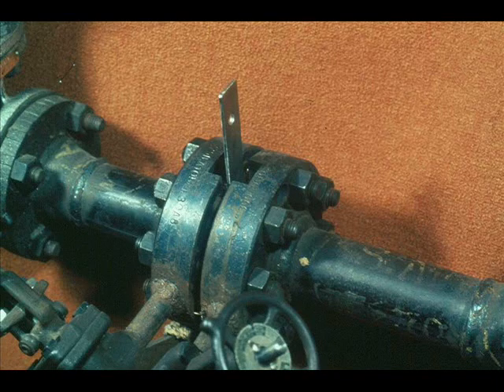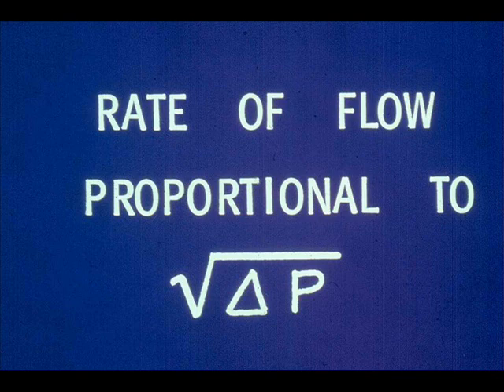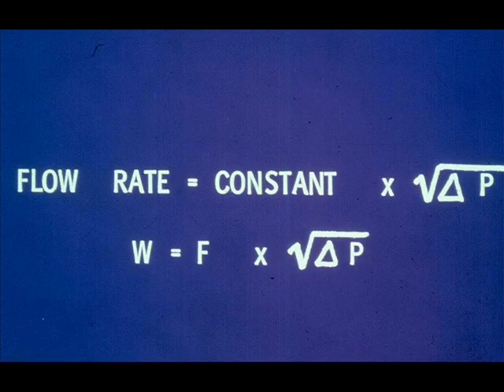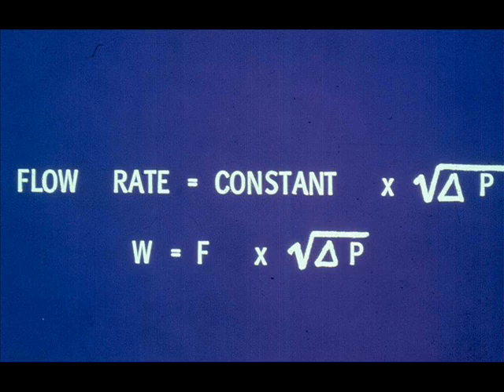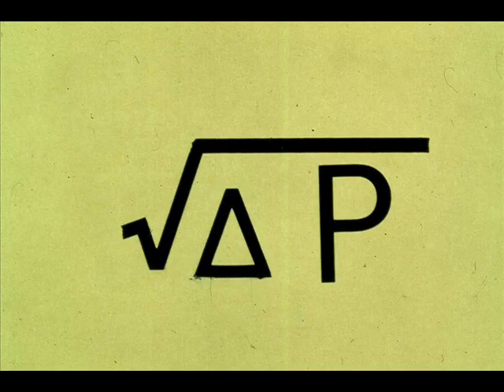For every particular orifice installation, the rate of flow can be calculated for any pressure drop or delta P measured by the meter. The rate of flow is proportional to the square root of the delta P. Expressed mathematically, the flow rate W equals a constant F multiplied by the square root of the delta P. The constant F can be determined for an orifice installation and is called the meter constant. Taking the square root of every measured delta P is time-consuming, so the meter scale is constructed to read the square root directly.